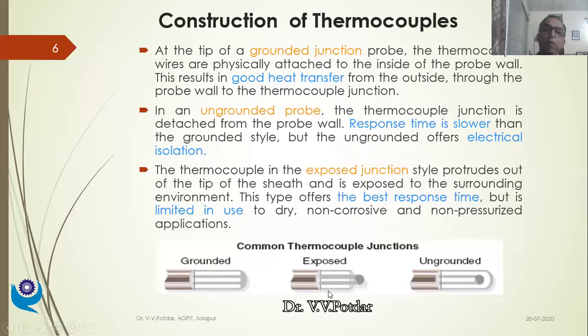In an ungrounded probe, I don't have grounding. In an ungrounded probe, the thermocouple junction is detached from the probe wall. The response time is slower because the heat transfer is lower than in the grounded style, but the ungrounded probe offers electrical isolation. This is the benefit of the ungrounded probe, but the response time is slower. It will take much more time to respond.